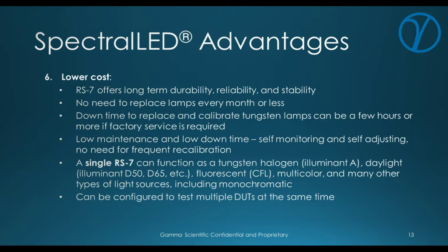And the cost, lastly, is going to be lower, especially when you consider the long-term durability and uptime that it's going to help you maintain. No needing to replace lamps, and you can also trust that the output is stable because it's self-monitoring. There's no doubt if there's any drift or any sort of system error has occurred. Because we have the optical feedback built in, we're going to be told in real time via an alarm if any given channel is no longer functioning or is not outputting as much energy as we expect. We can pull that type of information from the firmware.